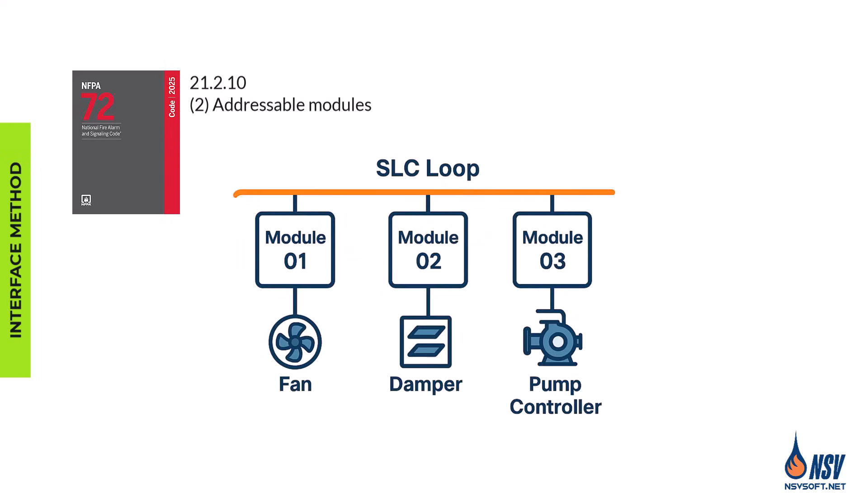Second method is addressable modules. In modern addressable fire alarm systems, specific input-output modules are used. Each module has a unique address, allowing for more granular control and monitoring of specific functions or devices from the FACP.